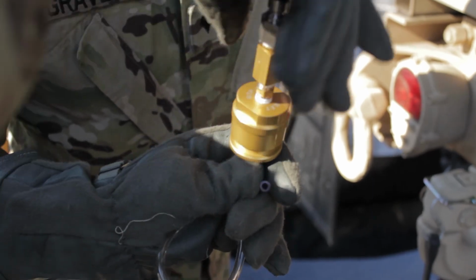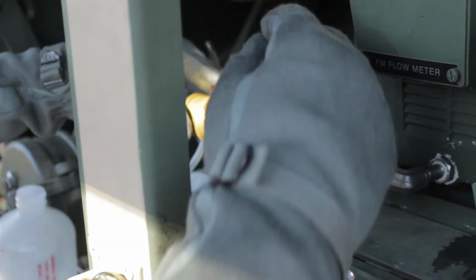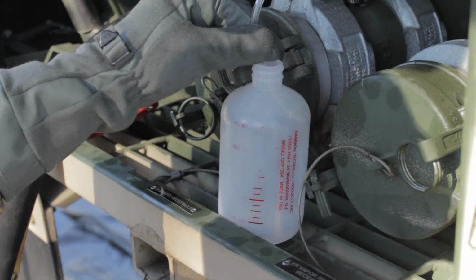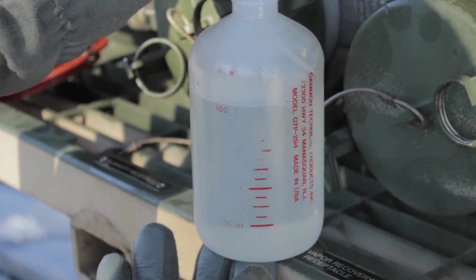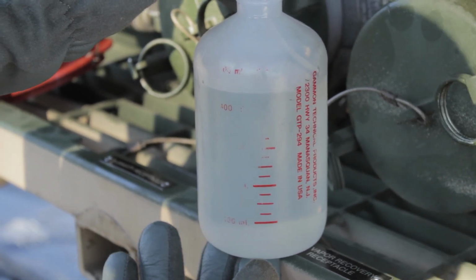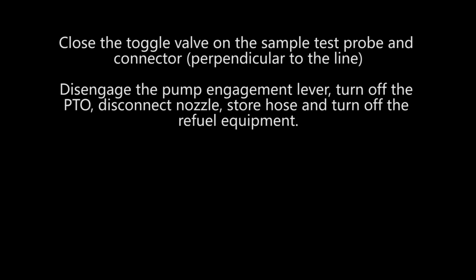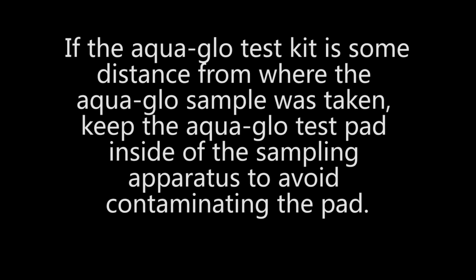Screw the pad holder assembly back together. Move the toggle valve on the sample test probe and the connector to the open position, parallel to the line. Allow 500 milliliters of fuel to flow through the sampling test probe into the clear container. Close the toggle valve on the sample test probe and connector perpendicular to the line. Disengage the pump engagement lever, turn off the PTO, disconnect nozzle, store hose, and turn off the refueling equipment. If the Aqua Glo test kit is some distance from where the Aqua Glo sample was taken, keep the Aqua Glo test pad inside the sampling apparatus to avoid contaminating the pad.